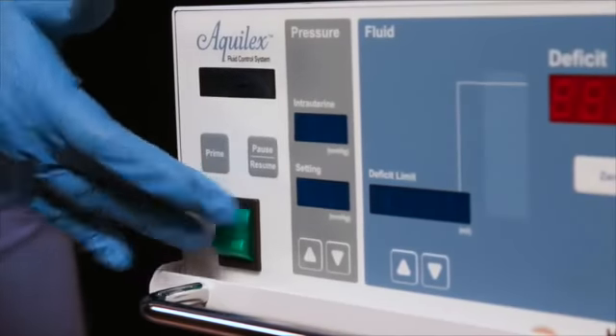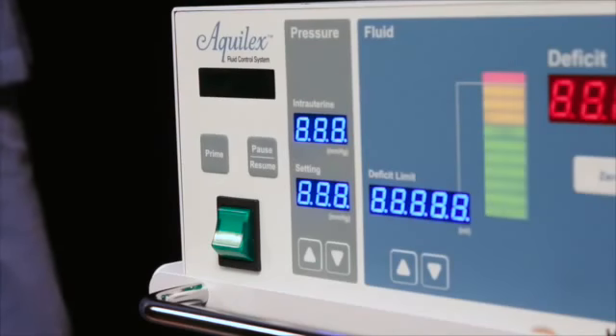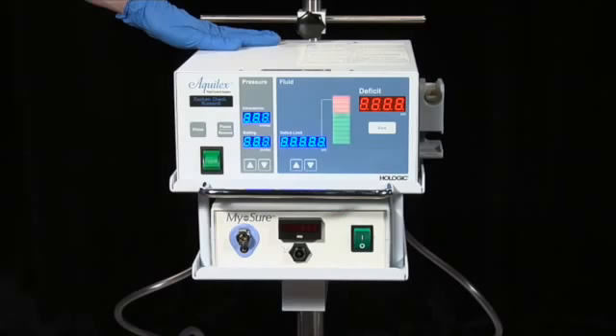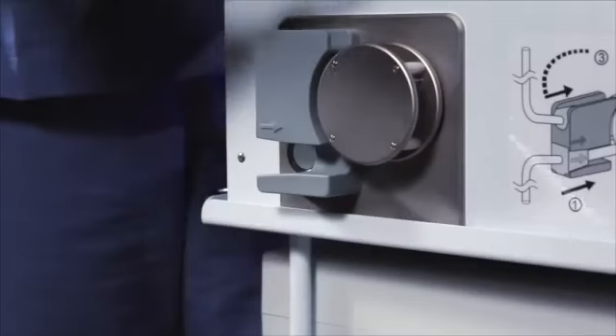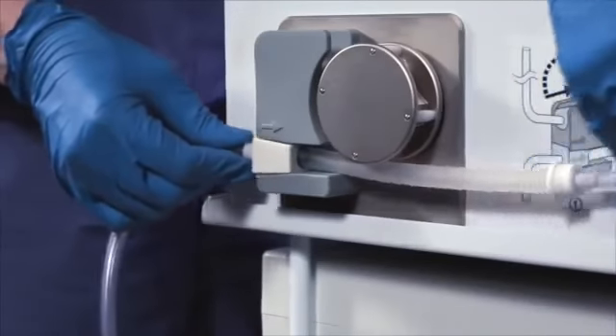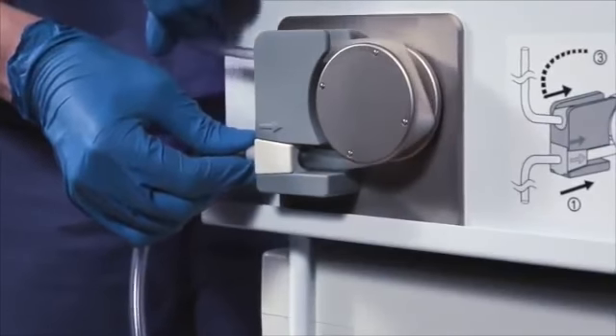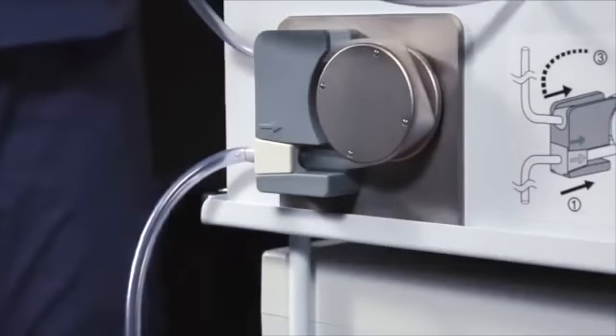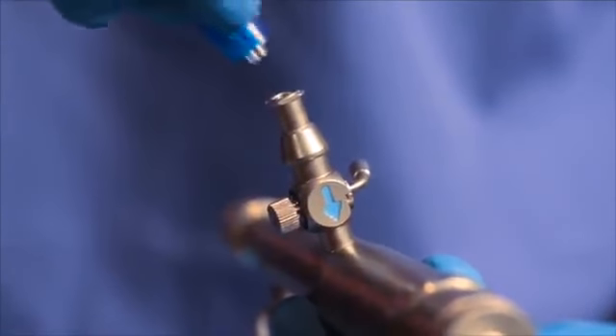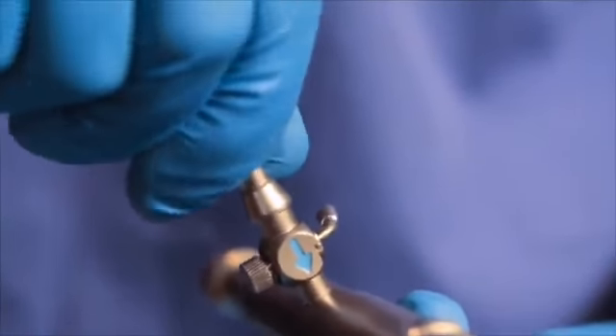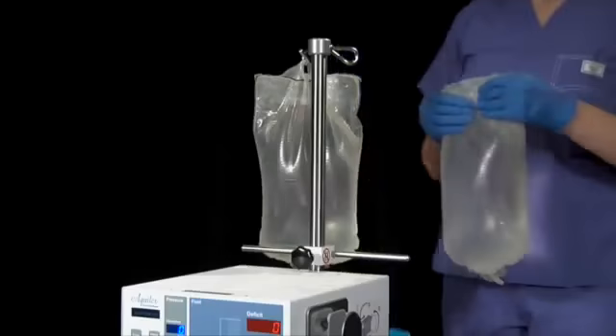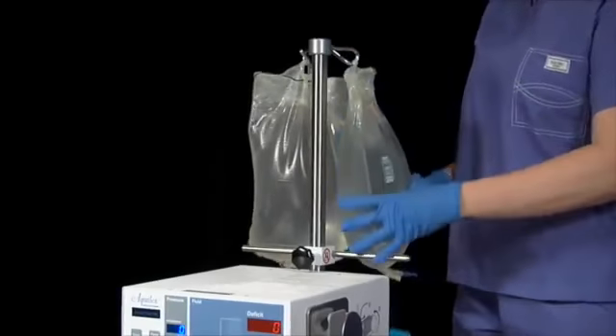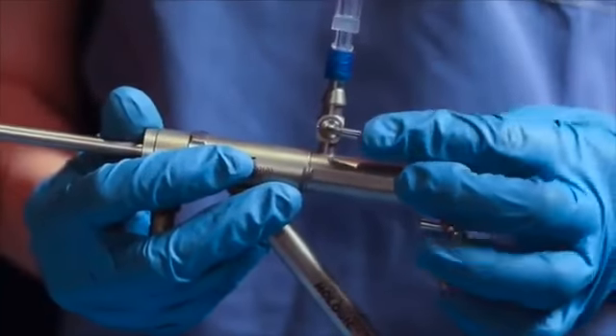Turn on the Aquilex fluid control system. The system will perform an automatic self-diagnostic test. Insert the inflow tubing into the pump head. Connect the blue Luer lock to the hysteroscope inflow channel marked by a blue arrow. Hang the fluid bags. Spike the bags. Open the inflow stopcock.